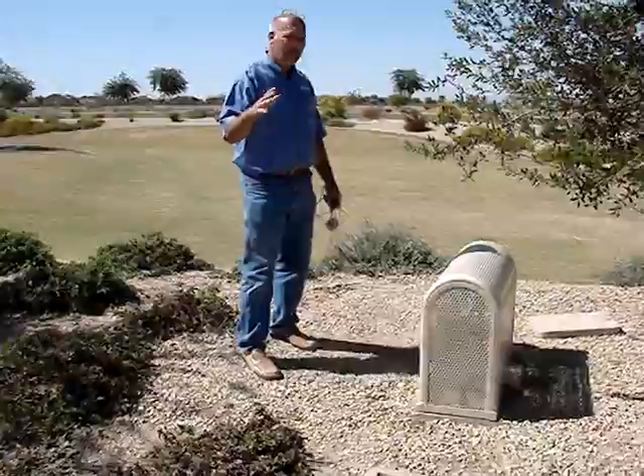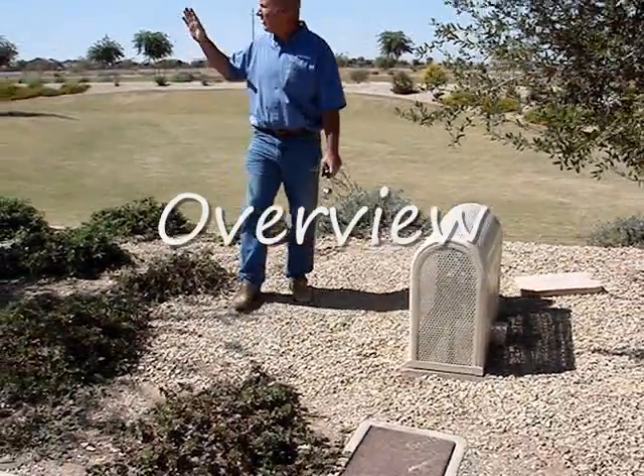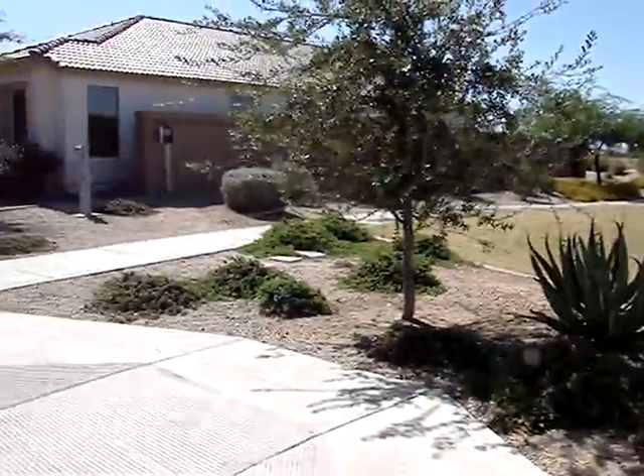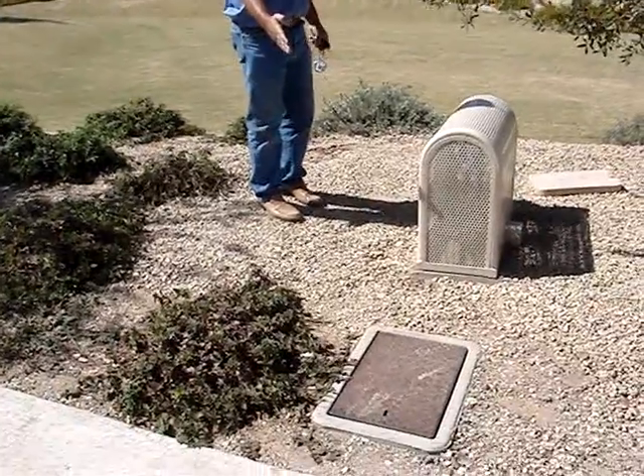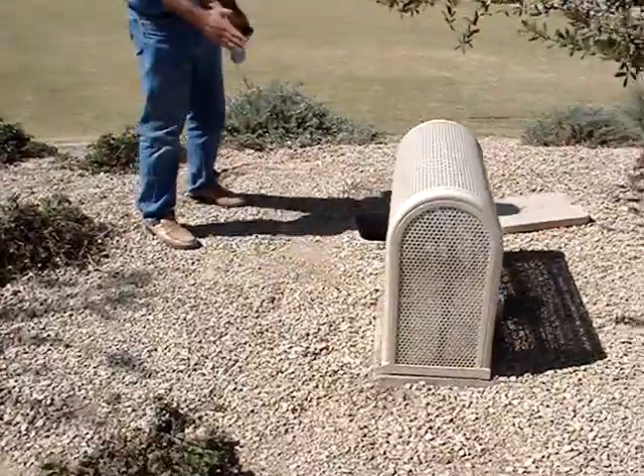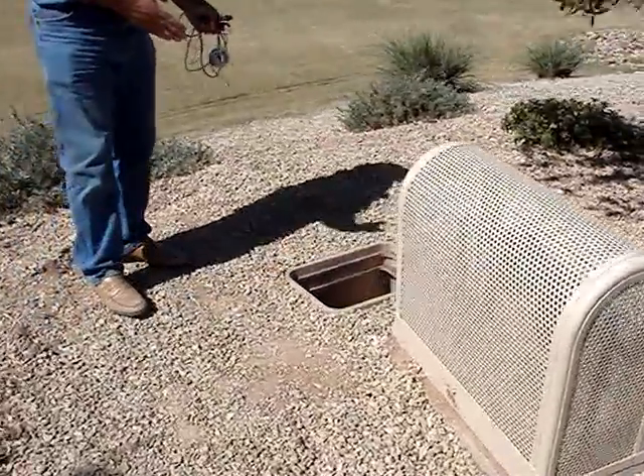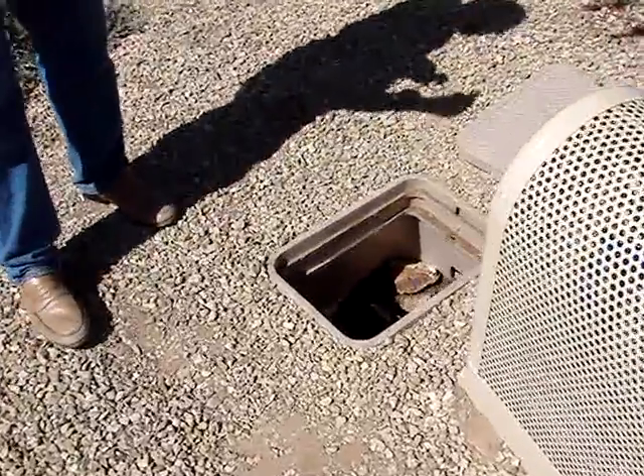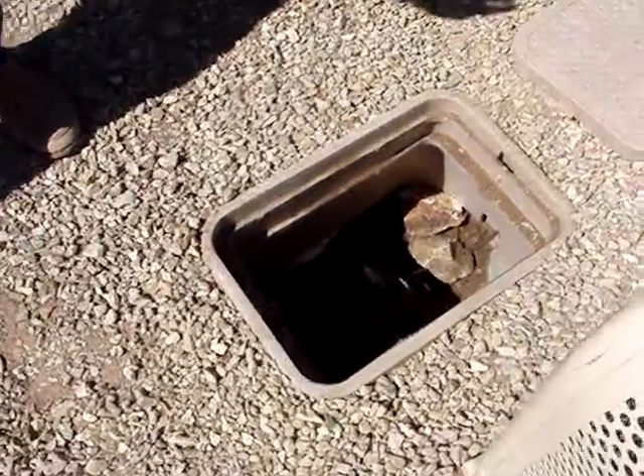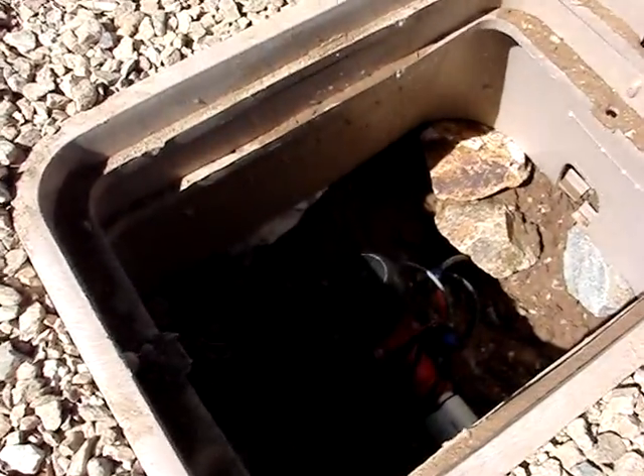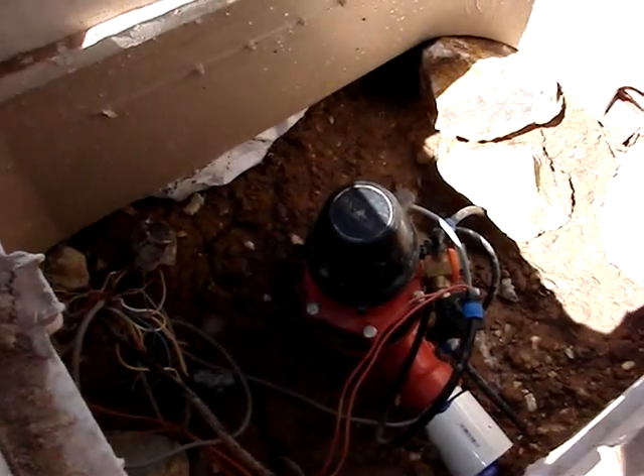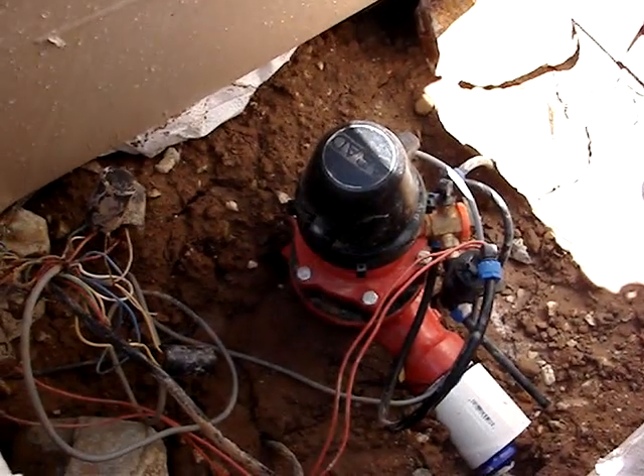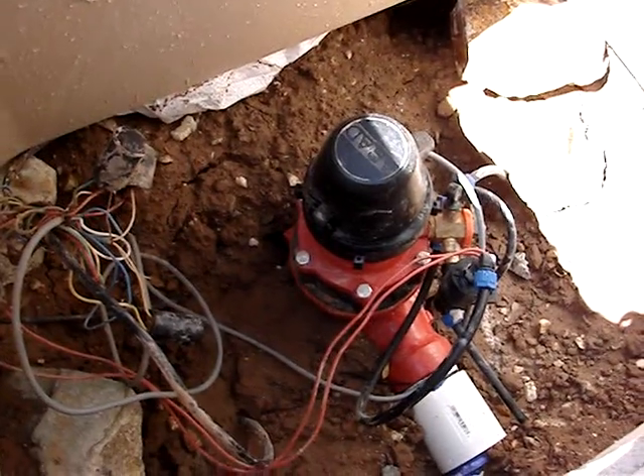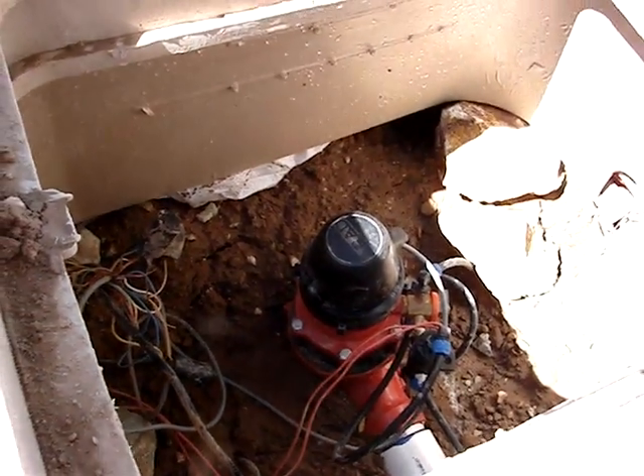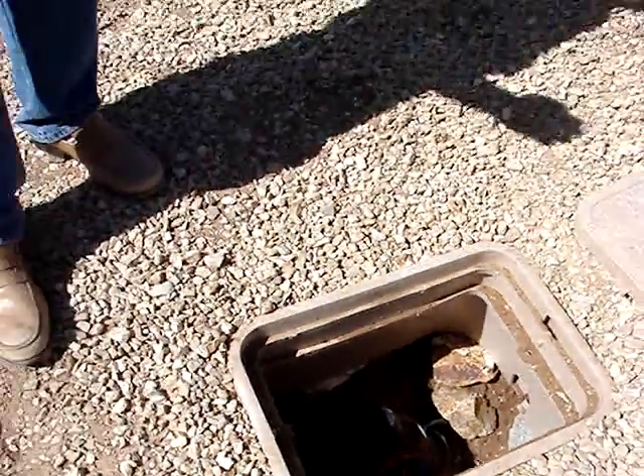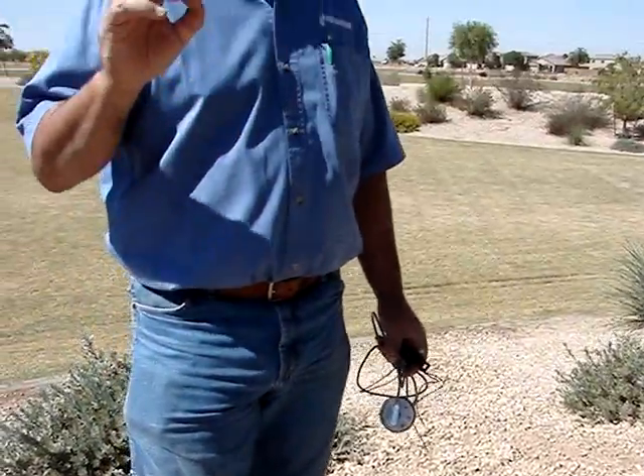Here we are at a typical retrofit installation where we have an ET clock. This one happens to be a Toro IntelliSense. We have a water meter from the street that they get billed on, a backflow preventer, and then we have our Netafim hydrometer, which is a master valve, a water meter, and a flow sensor all in one unit. The advantages are that there are 0 upstream and 0 downstream straight pipe requirements. It fits in one box and it goes right over to the clock. It's very accurate and it's repeatable. And the key is repeatability and accuracy because it eliminates false alarms.